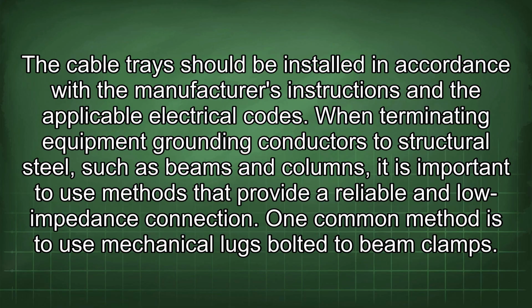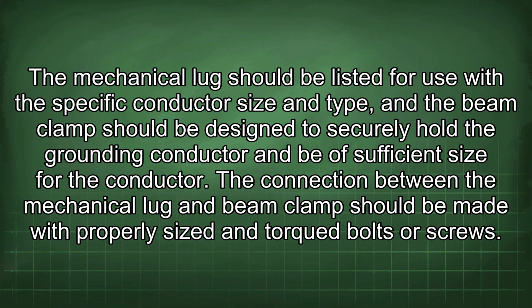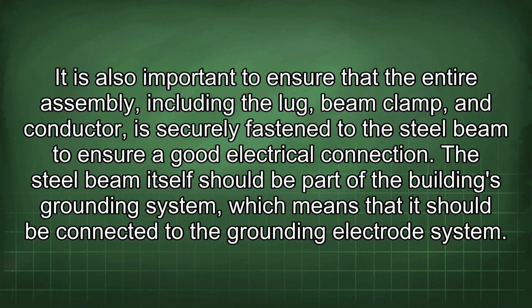When terminating equipment grounding conductors to structural steel, such as beams and columns, it is important to use methods that provide a reliable and low impedance connection. One common method is to use mechanical lugs bolted to beam clamps. The mechanical lug should be listed for use with the specific conductor size and type, and the beam clamp should be designed to securely hold the grounding conductor and be of sufficient size for the conductor. The connection between the mechanical lug and beam clamp should be made with properly sized and torqued bolts or screws. It is also important to ensure that the entire assembly, including the lug, beam clamp, and conductor, is securely fastened to the steel beam to ensure a good electrical connection.